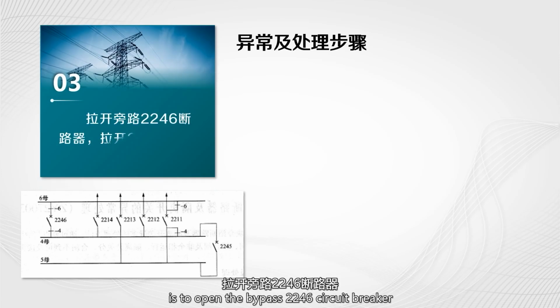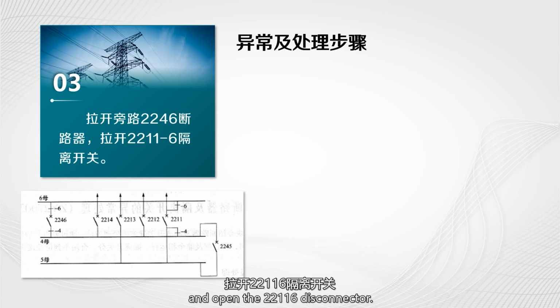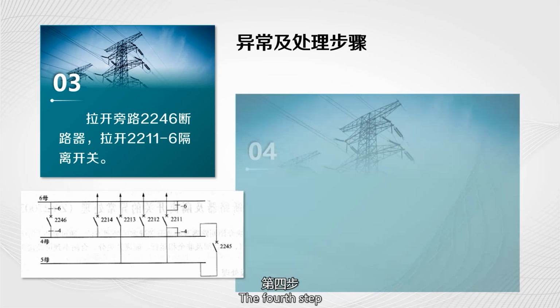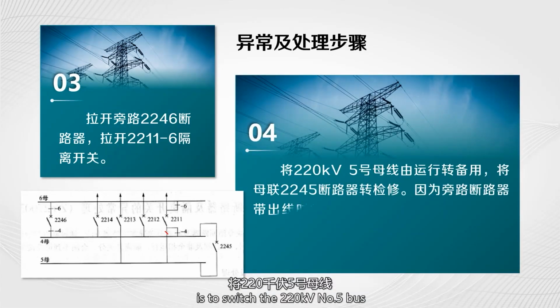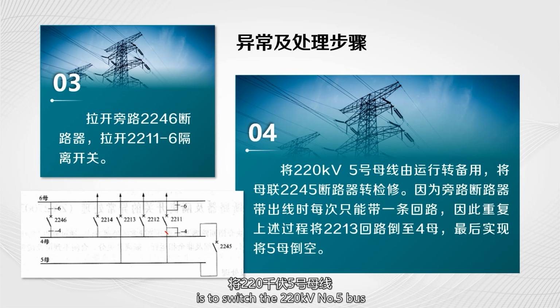The third step is to open the bypass 2246 circuit breaker and open the 2211-6 disconnector. The fourth step is to switch the 220 kV number 5 bus from operating to standby mode and switch the bus tie 2245 circuit breaker to maintenance mode. Because the bypass circuit breaker can only carry one circuit at a time, repeat the above process to invert the 2213 circuit to the number 4 bus. Finally, the number 5 bus was emptied.